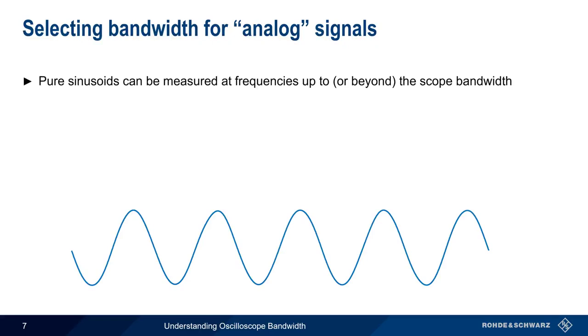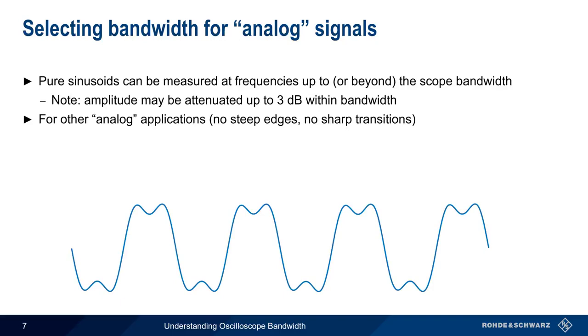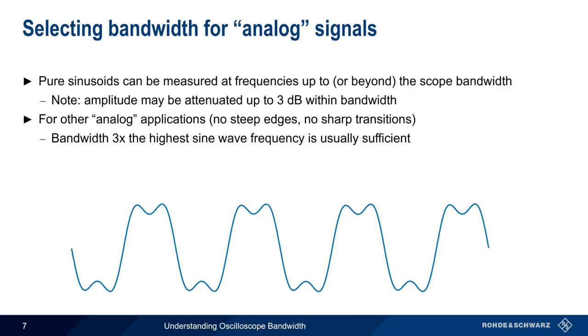Selecting an appropriate bandwidth for analog signals is actually rather straightforward. A purely sinusoidal signal can be measured at frequencies up to, and even beyond, the scope's bandwidth. The shape of the waveform won't be significantly distorted, but the amplitude may be attenuated up to 3 dB as the bandwidth limit is approached, and will be attenuated even more once the bandwidth limit is crossed. For other analog signals — that is, signals without steep edges or sharp transitions — a bandwidth of 3 times the highest sine wave frequency is usually sufficient to avoid serious distortion. Using a bandwidth of 3x means our scope should be able to accurately measure the fundamental, second harmonic, and third harmonic. We'll talk more about harmonics on the next slide.